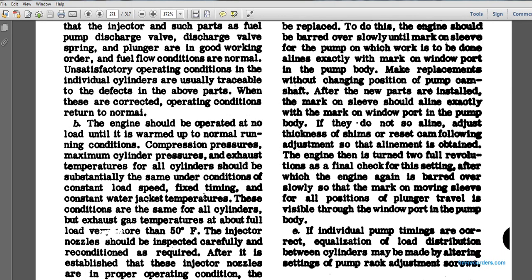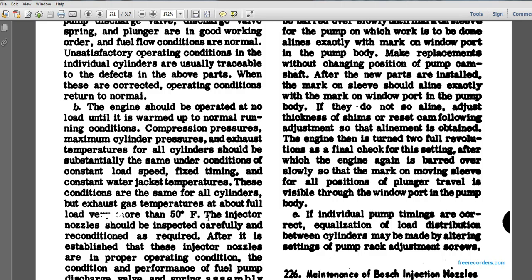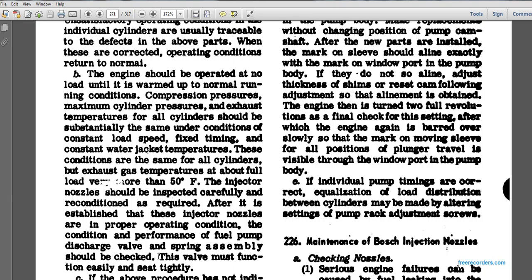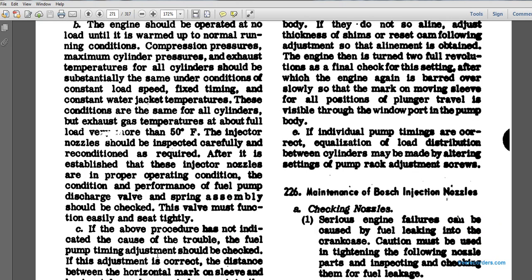The engine should be operated at no load until it warms up to normal running condition. Compression pressure, maximum cylinder pressure and exhaust temperature for all cylinders should be substantially the same under conditions of constant load, speed, fixed timing and constant water jacket temperatures, where these conditions are the same for all the cylinders. But exhaust gas temperatures at about full load vary more than 50 degrees Fahrenheit. The injector nozzle should be inspected carefully and reconditioned as required. After it is established that the injector nozzles are in proper operating condition, the performance of the fuel pump discharge valve and spring assembly should be checked. The valve must function easily and seat tightly.